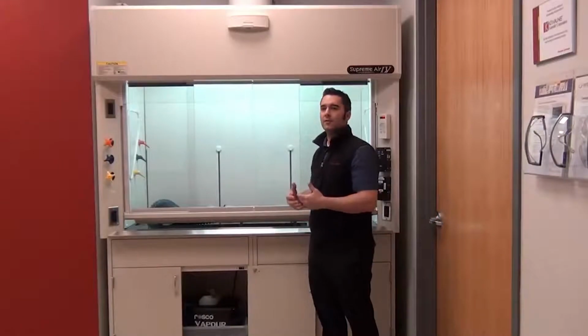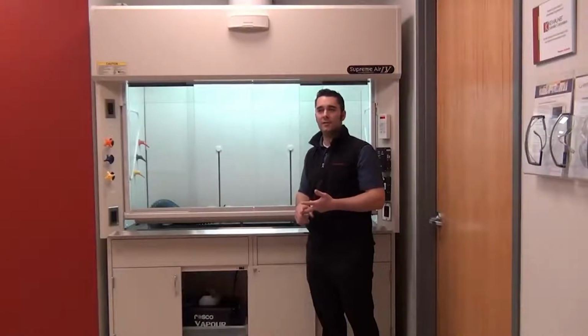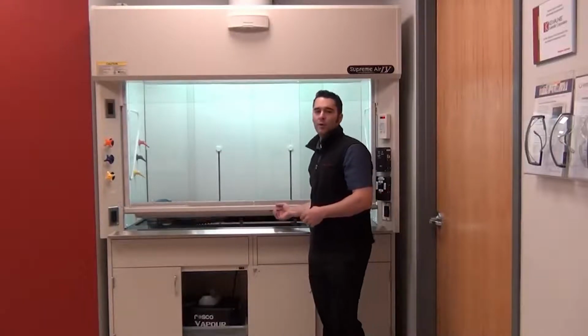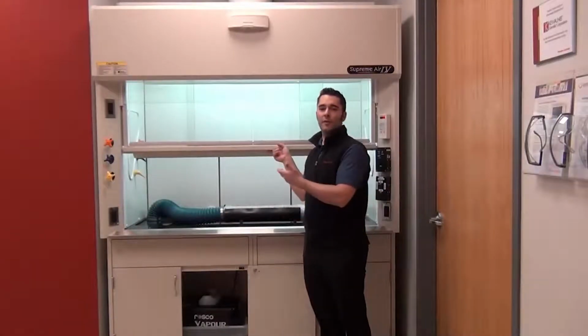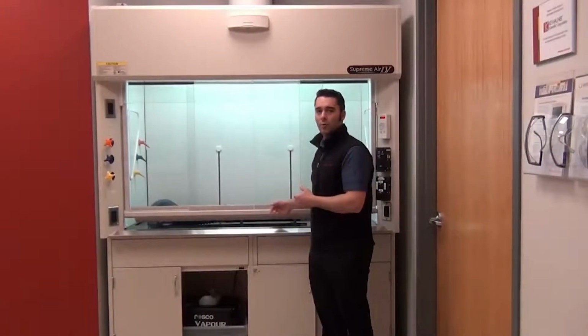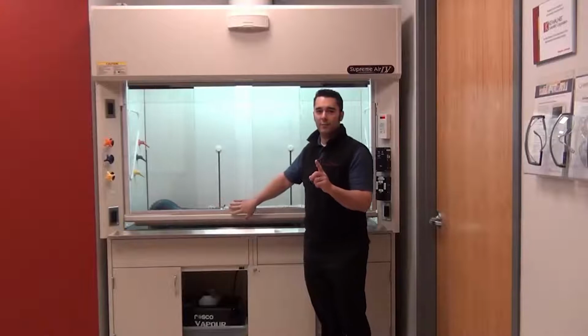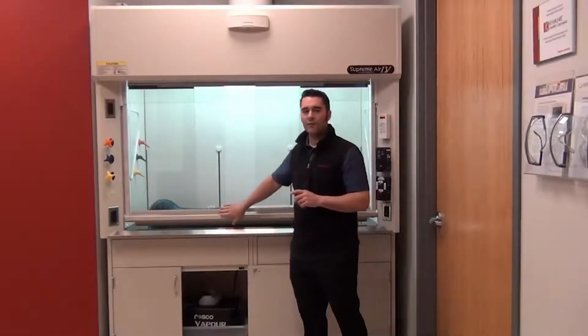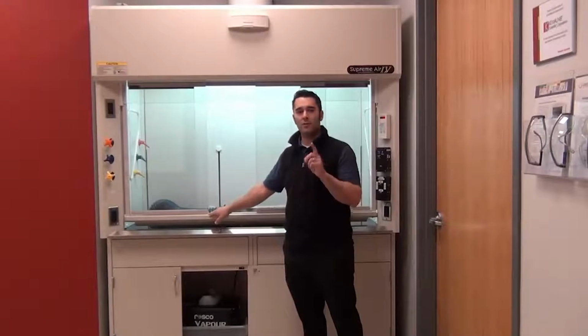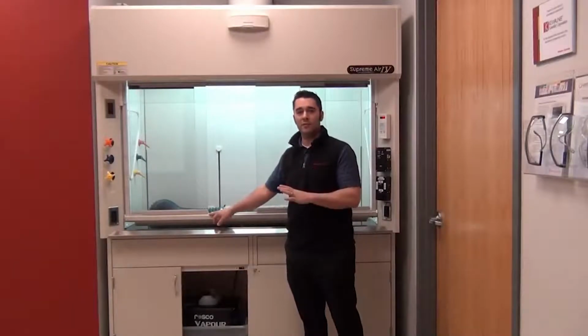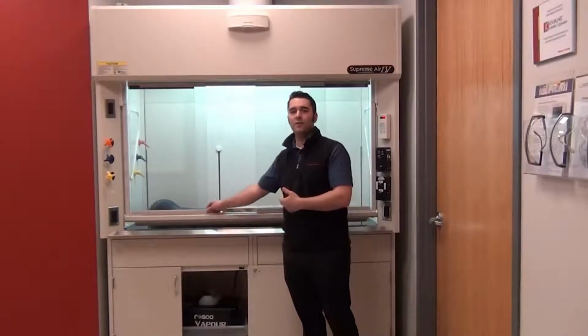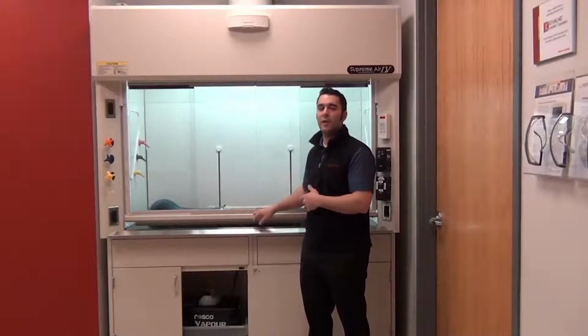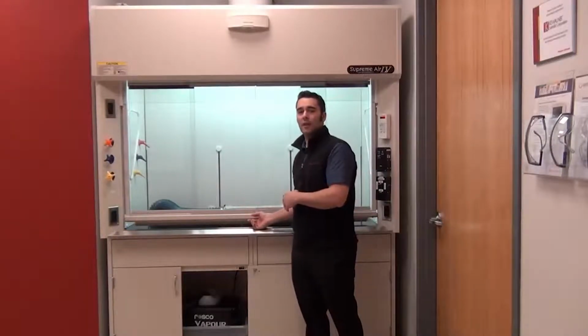So the three things that Phoenix Controls really does for the safety aspect of fume hoods by using our valves and our sash sensing technology is giving the customer the fastest speed of response. So the ability for the fume hood valve to react to a movement in the sash position, whether it's vertical or horizontal, within 1 second speed of response. So that means if I move this sash, by the time I stop moving the sash, within 1 second, my Phoenix valve is going to finish positioning itself and be in a steady state.